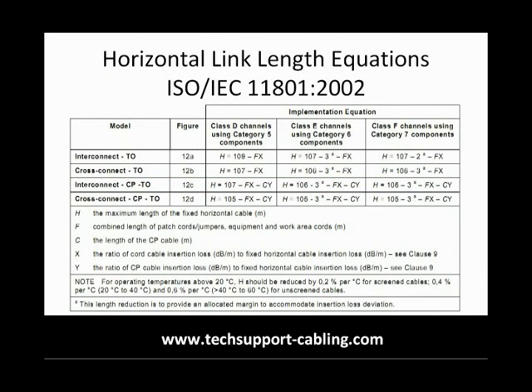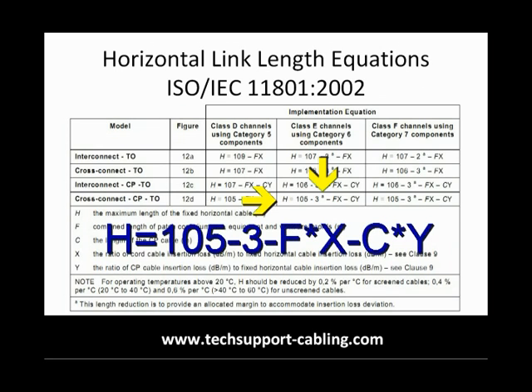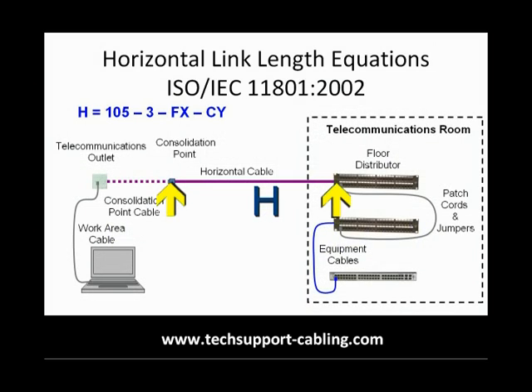Following down and across the appropriate column and row gives us the formula: H equals 105 minus 3, minus F times X, minus C times Y — where H is the longest permissible length of the horizontal cable.